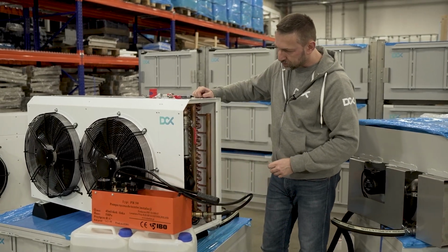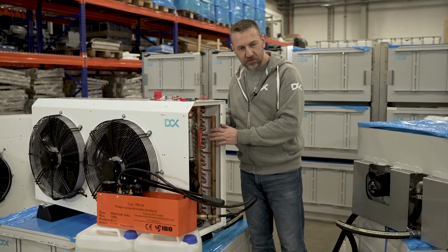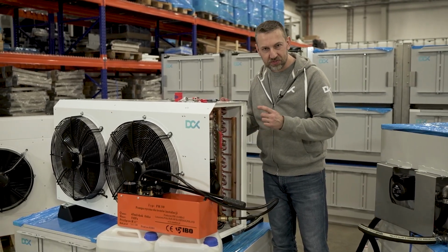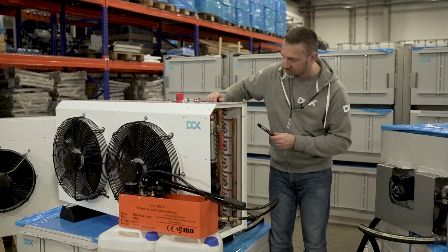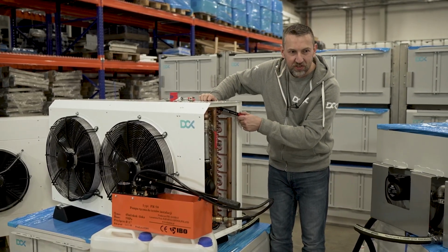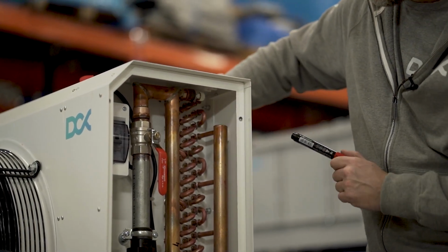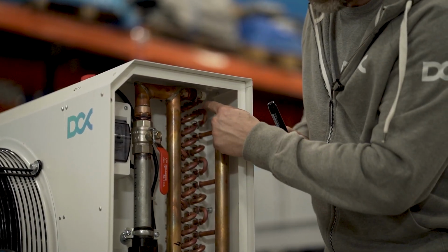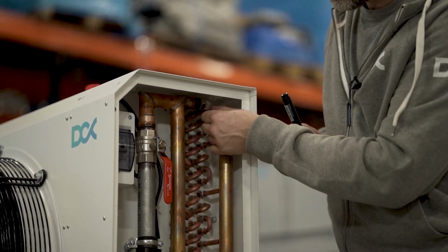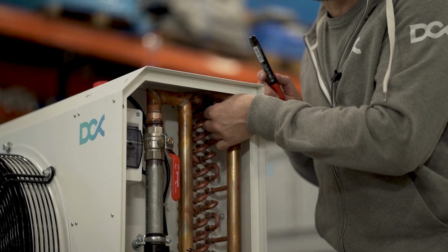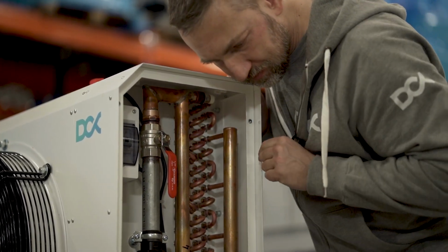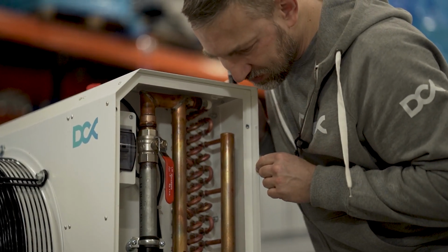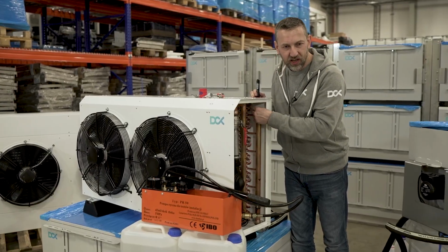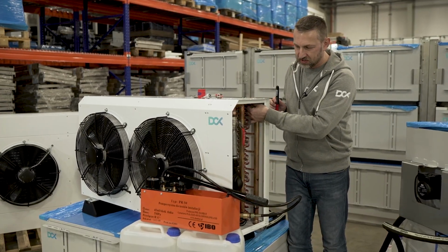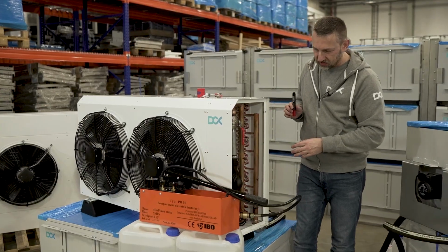the system. Now, the current units are equipped with the automatic vent, and you can observe what's happening here. And I need you to see here and observe here. If there is any dripping, you will see what is happening. That's just fine. It will drip from the air vent. So there is an air vent, and please observe, or hear, when I open that. Just a moment. You can hear the air being removed from every pocket, every coil there is on that unit, and it's an automatic air vent. So if you open that just a little bit, you'll be able to release the excess air.